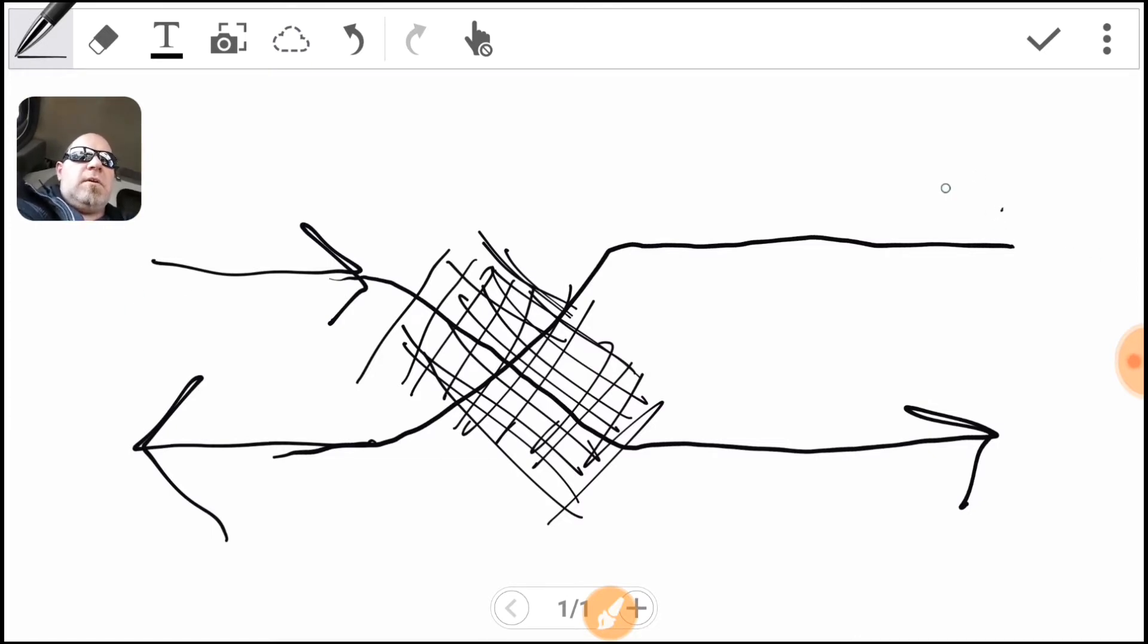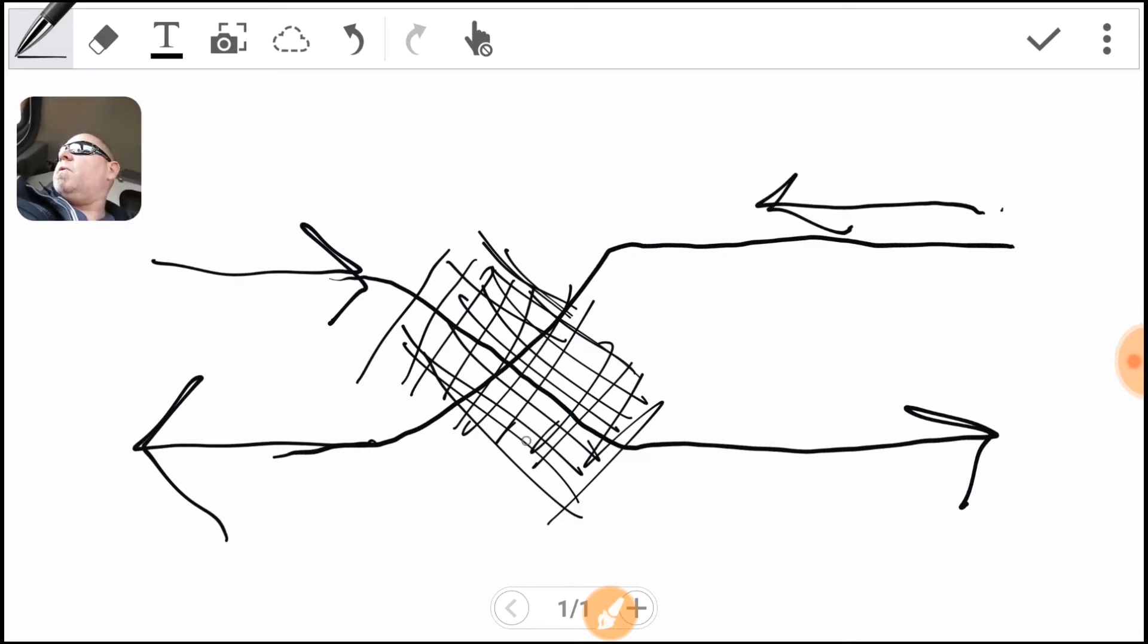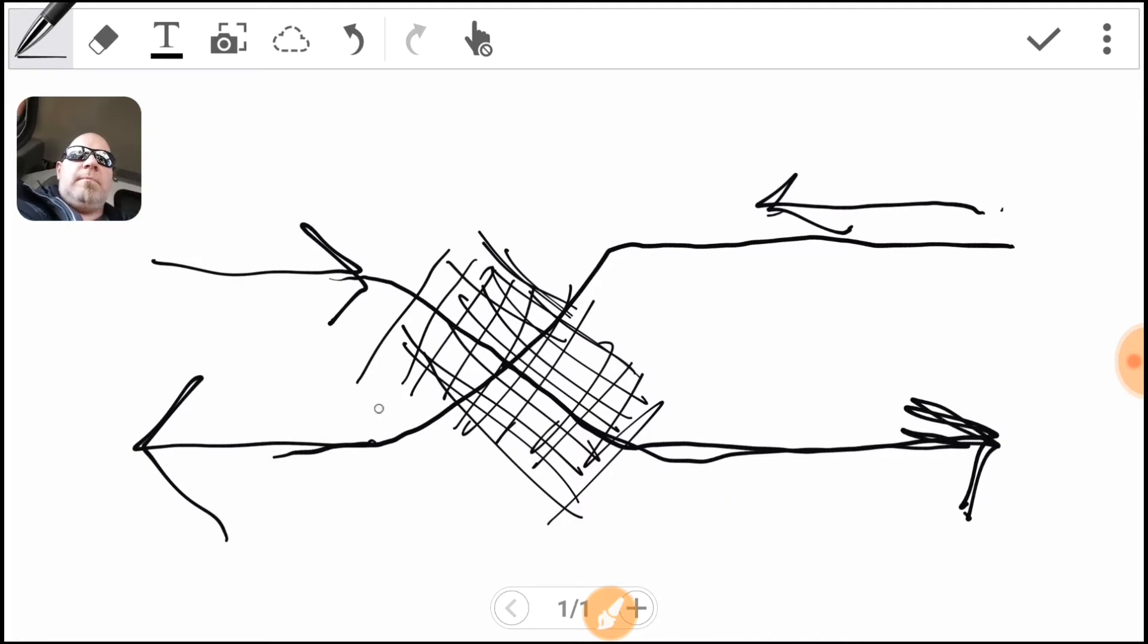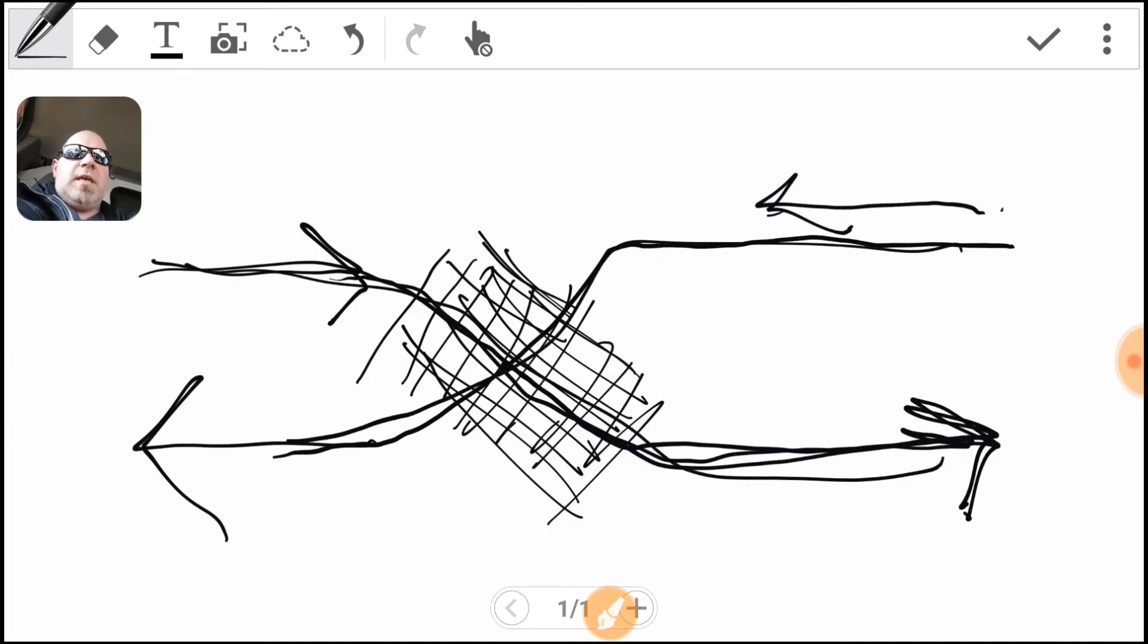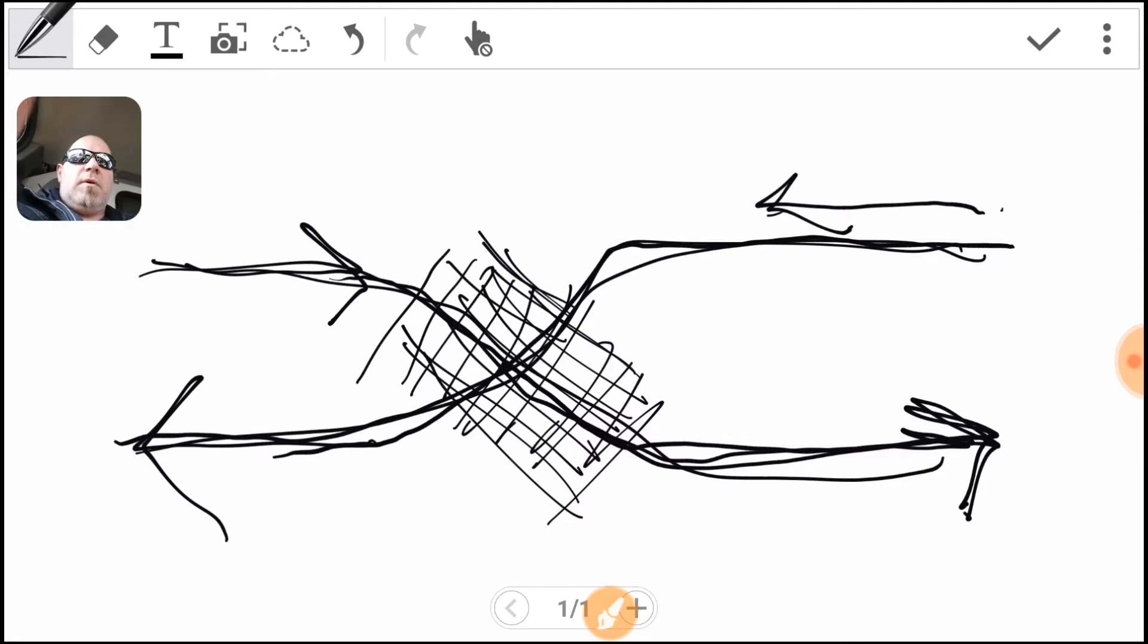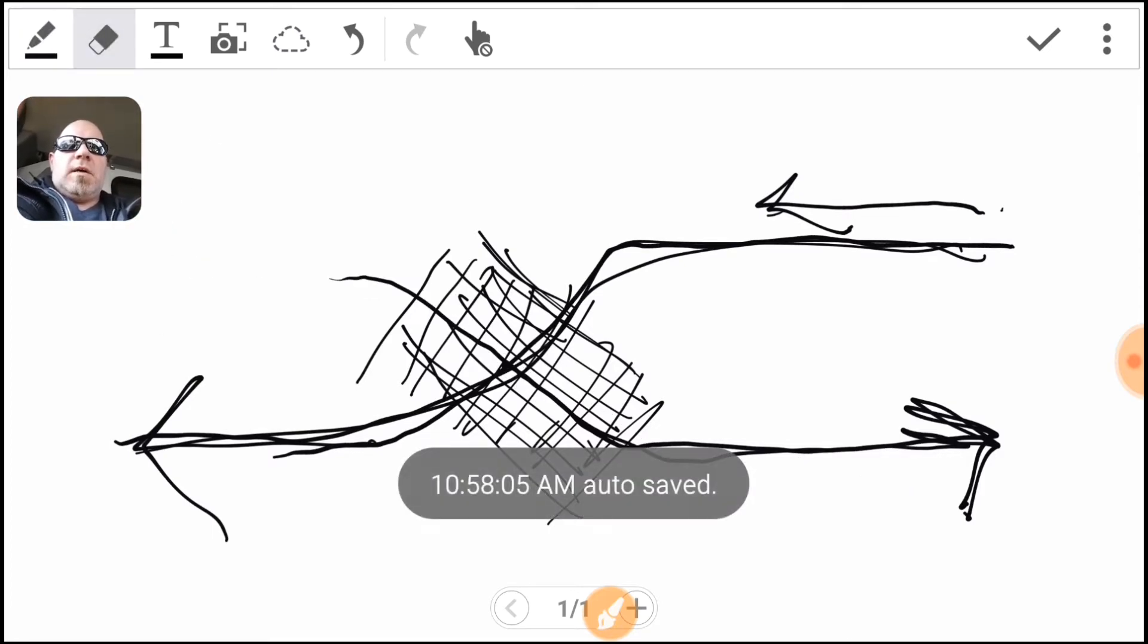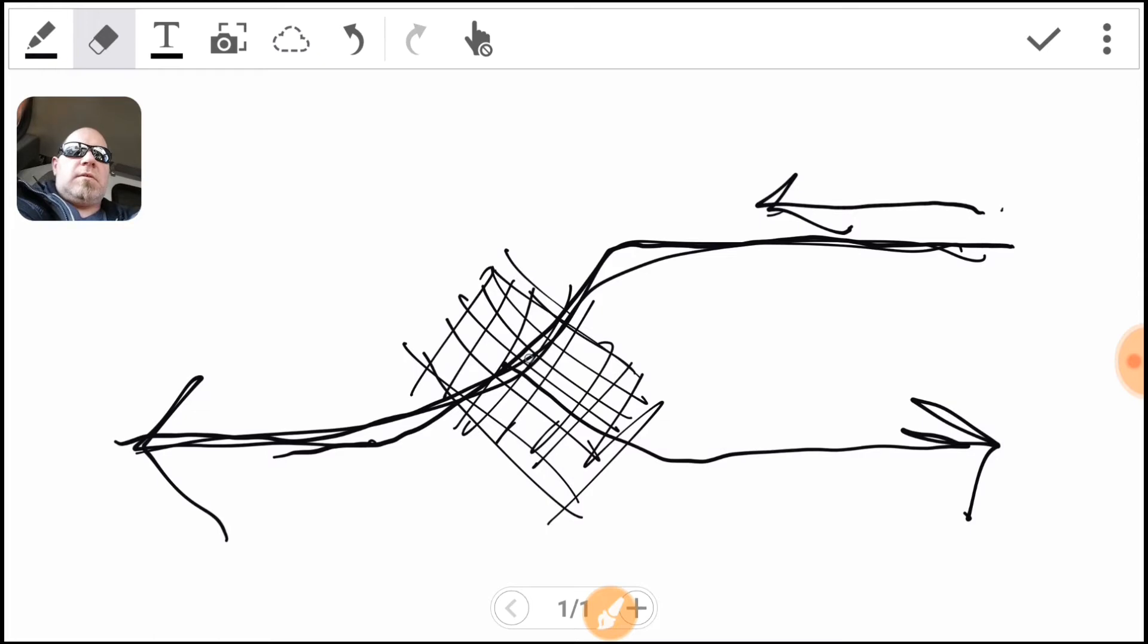So the media, and I'll draw a little closer detail of that media, but basically as the air is leaving it comes in contact through an exchanger and that heat will then transfer into this line and go back into the building. So basically it pre-warms the air coming in as it pulls the heat out of the air that's leaving the building.